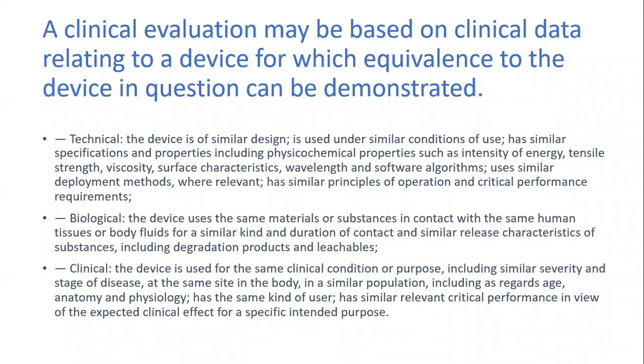So you have to establish the equivalency for your product with the benchmark product with which you're trying to demonstrate the equivalency. So for technical, the device should be of similar design. It has to be used under similar conditions of use. It has similar specifications and properties, which include physicochemical properties, such as, these are just the examples which are given.